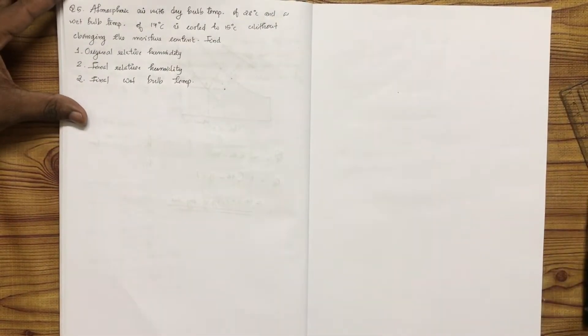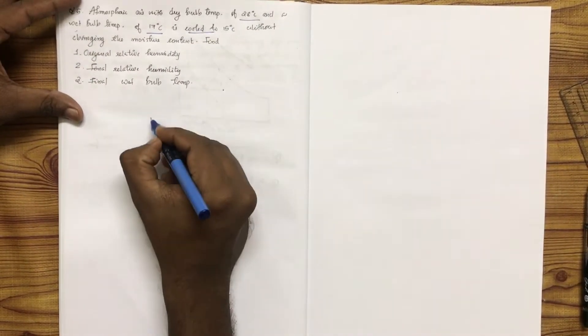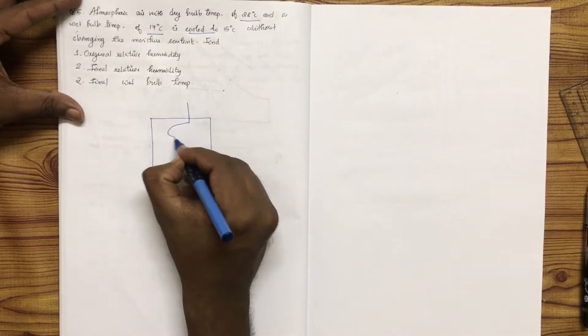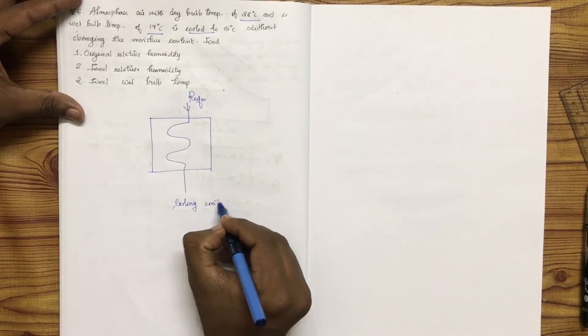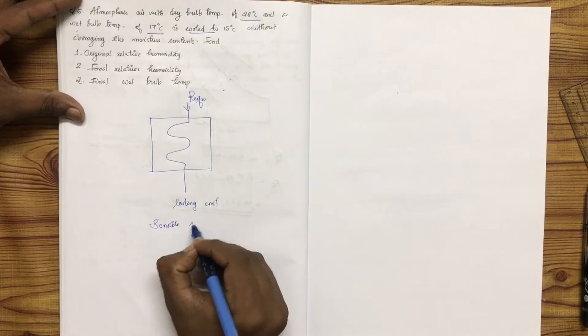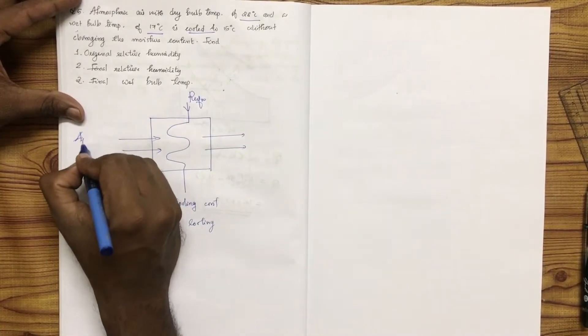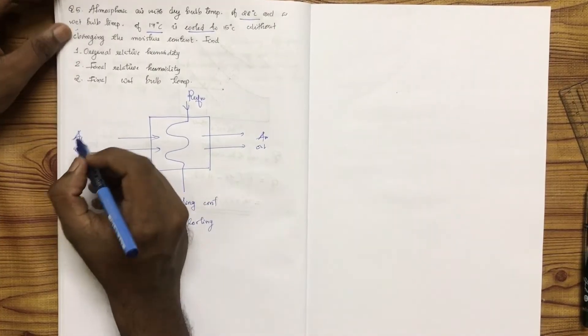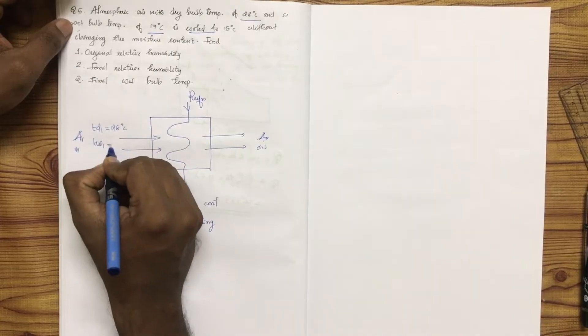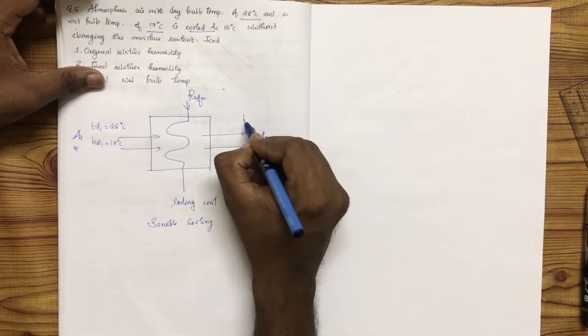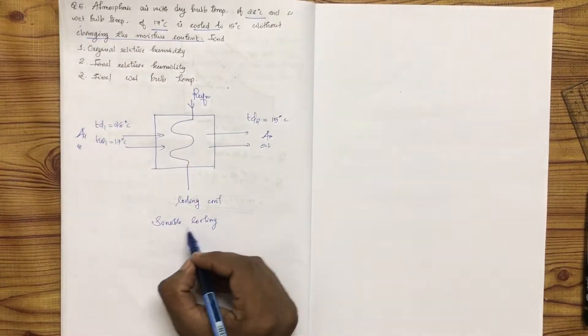This is an atmosphere with dry bulb temperature of 28 degrees Celsius and wet bulb temperature of 17 degrees Celsius. The atmospheric air with dry bulb temperature Td1 is equal to 28 degrees Celsius, and the wet bulb temperature is equal to 17. It is cooled to 15 degrees Celsius, so Td2 is equal to 15 degrees Celsius, without changing the moisture content. It will be sensible cooling.